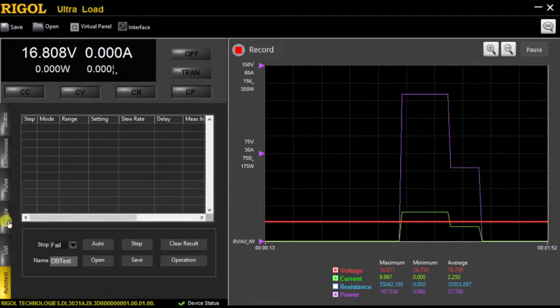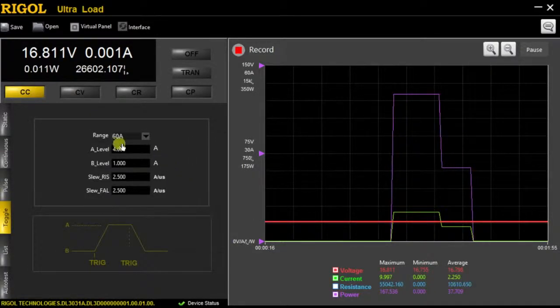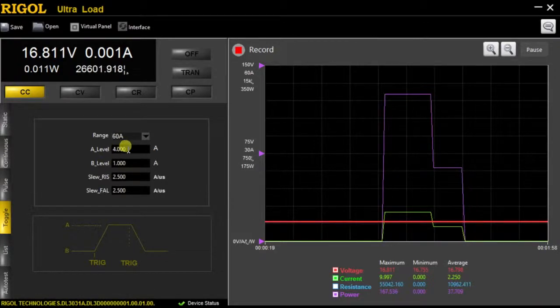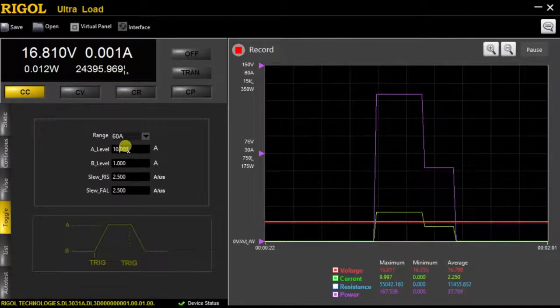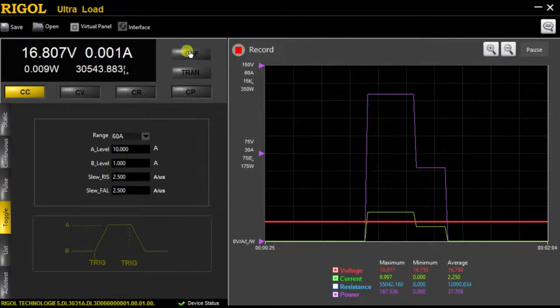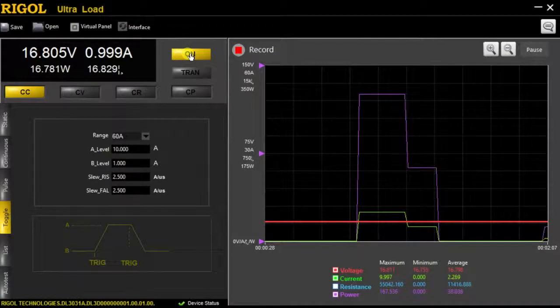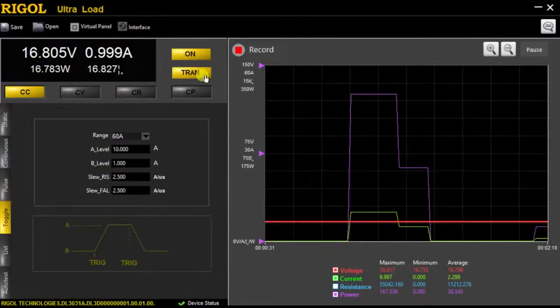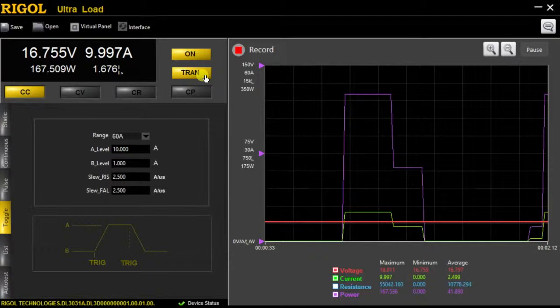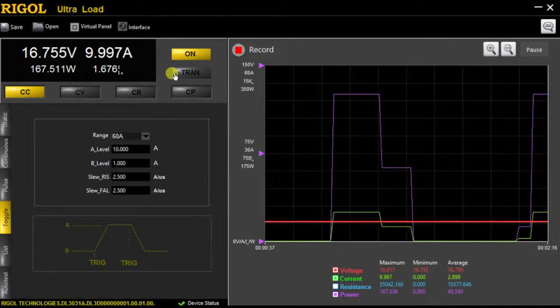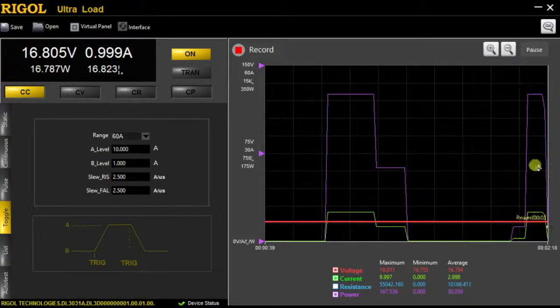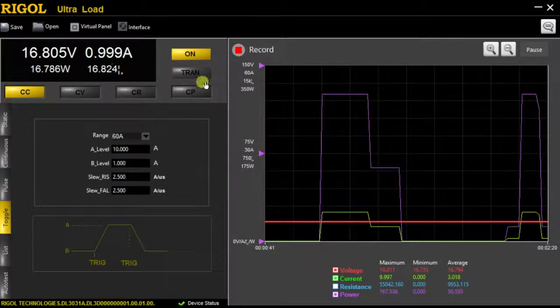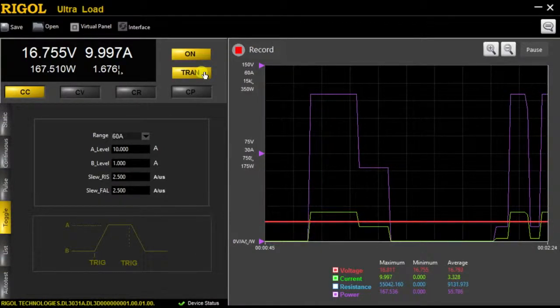But for the toggle state, we can go in, just like on the load itself, we can choose our level A, level B. So let's change level A to ten amps, and we'll keep level B at one amp. And then I can turn this on again, and just like on the instrument itself, in order to trigger the event, I hit the Tran button. And we'll see a spike up here until I trigger it to turn off, and now we'll see it decrease once again. And we can continue the same function, just like how it would on the load itself.